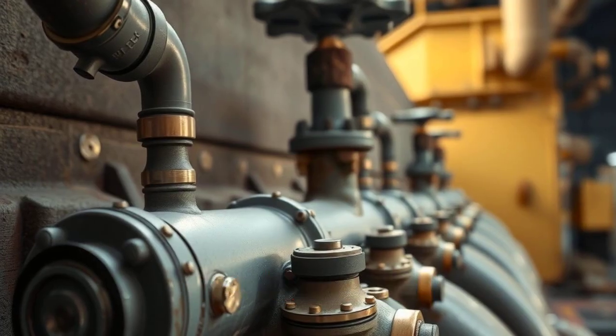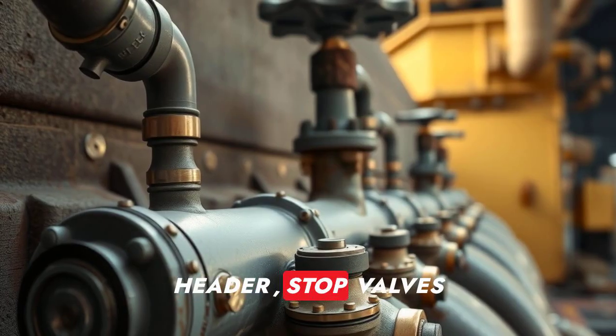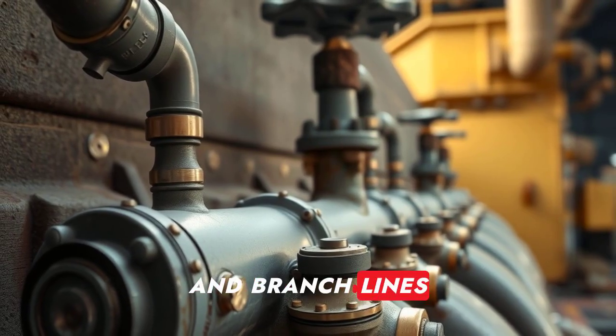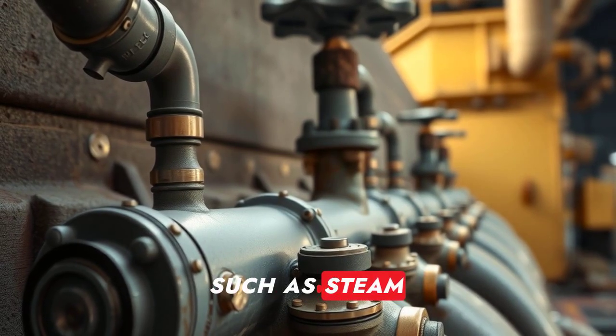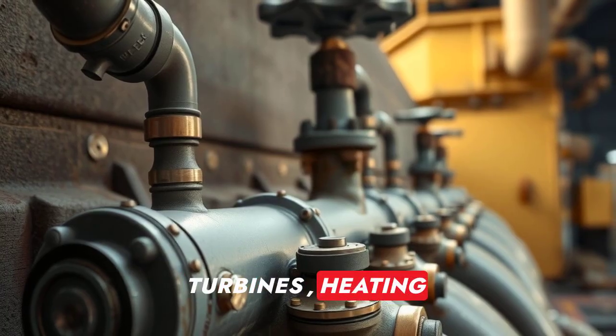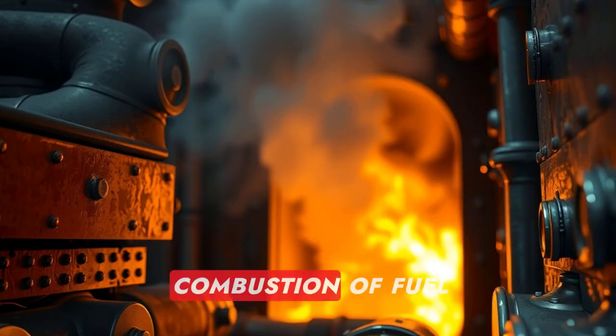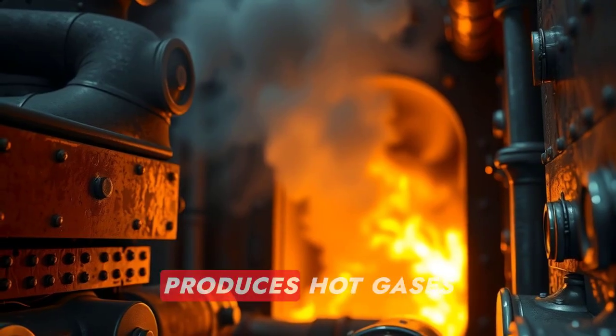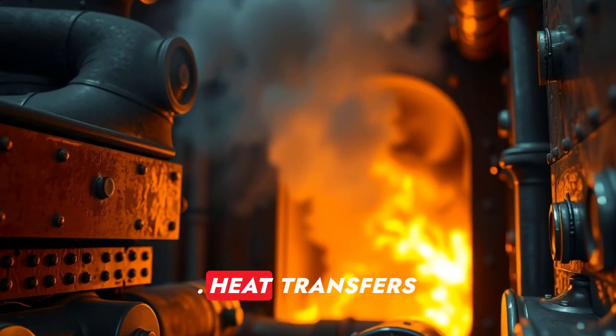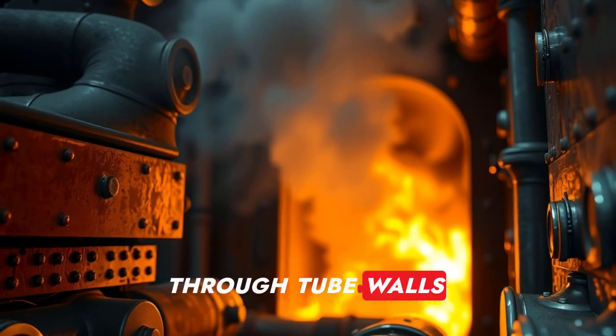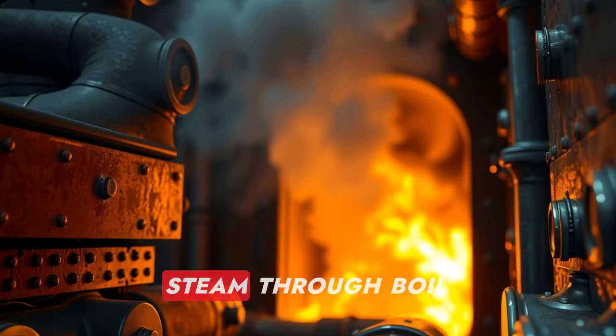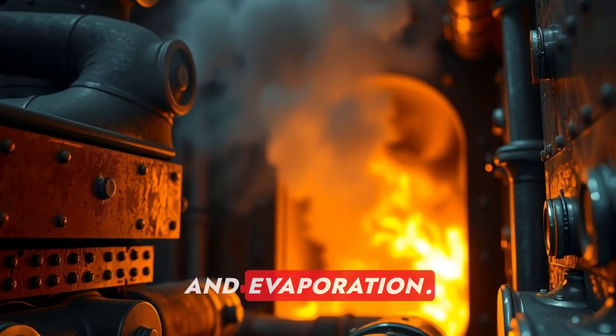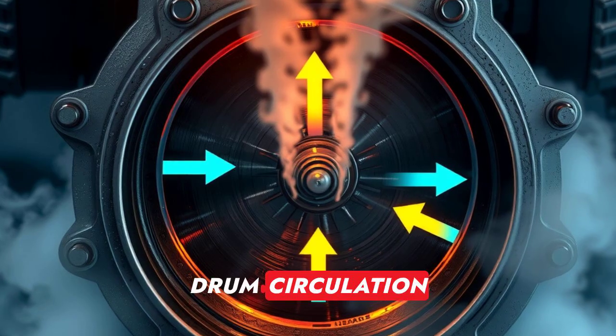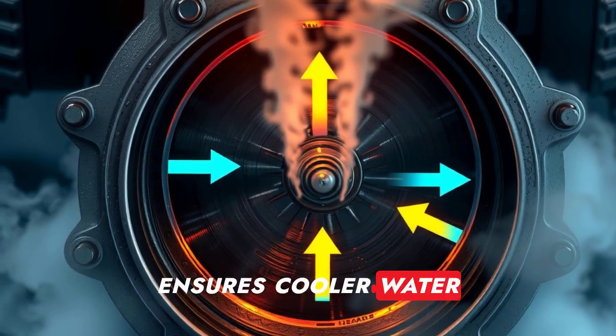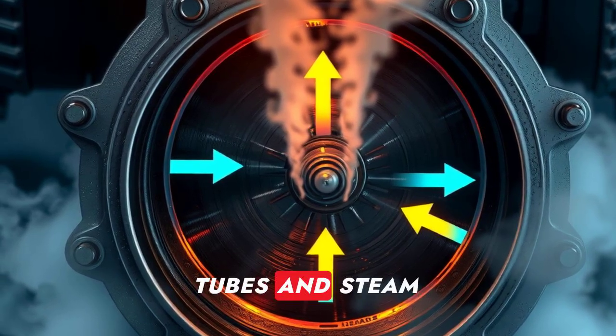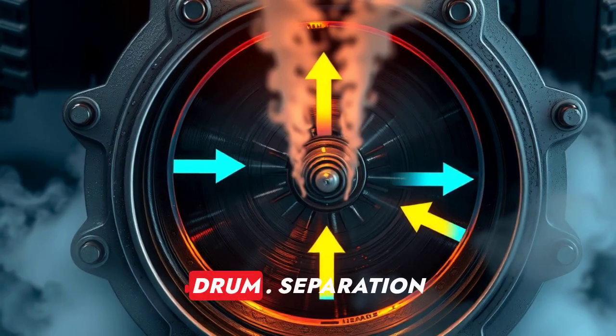Steam distribution includes the steam header, stop valves, and branch lines to service points such as steam turbines, heating and cargo systems. Combustion of fuel in the furnace produces hot gases. Heat transfers through tube walls to water, creating steam through boiling and evaporation. Drum circulation ensures cooler water flows to heated tubes and steam rises to the steam drum.